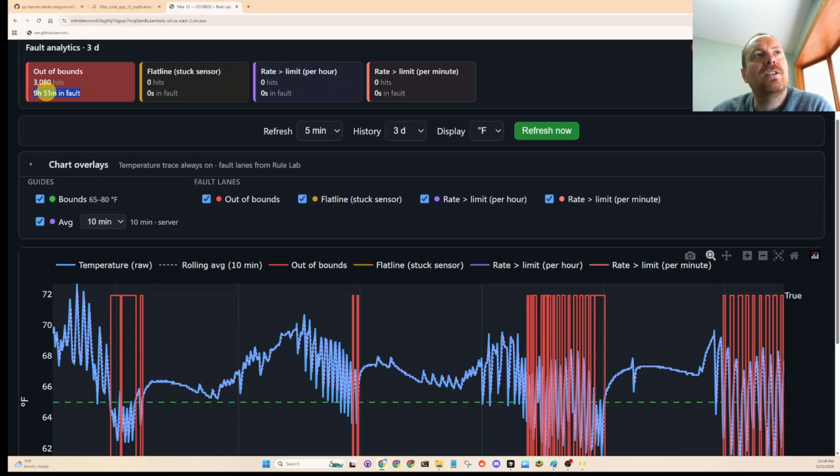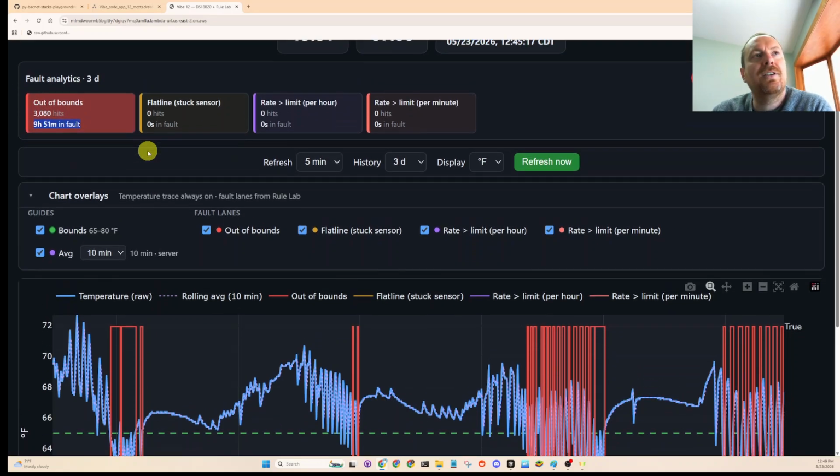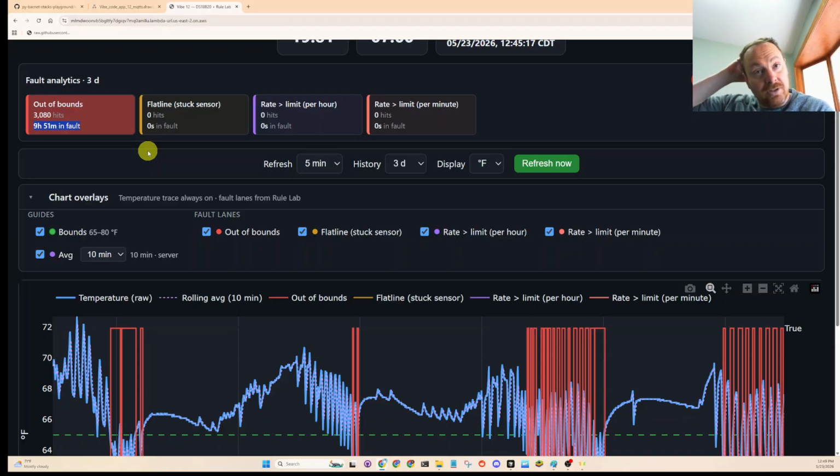If you can log elapsed time in some more advanced mechanical fault, that's where the mechanical engineer can then estimate some unit of power perhaps, and then multiply it by time, and then you have kilowatt-hours, and then they can equate that to dollars, and then eventually to estimating what it would cost to fix that issue, and now you can do an ROI or an investment return.